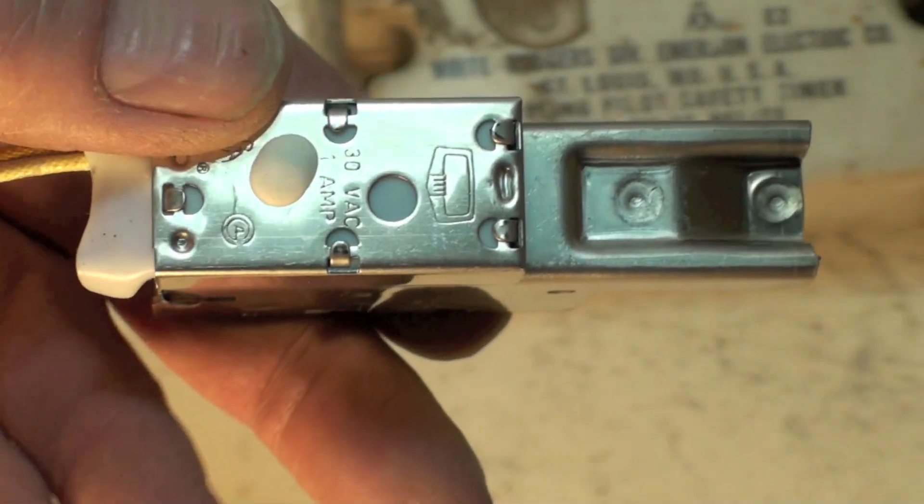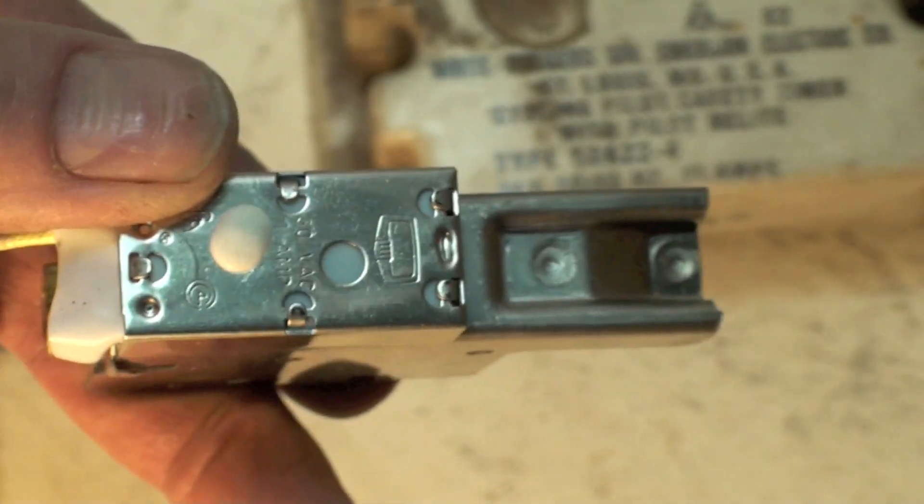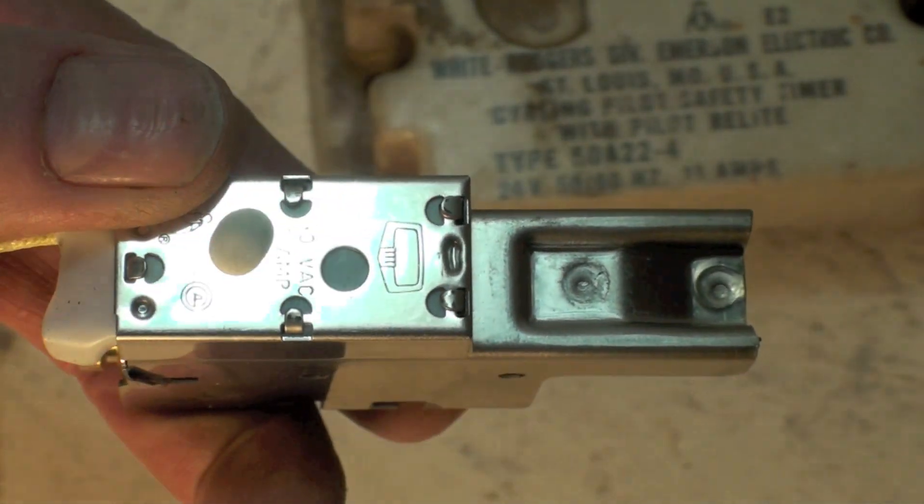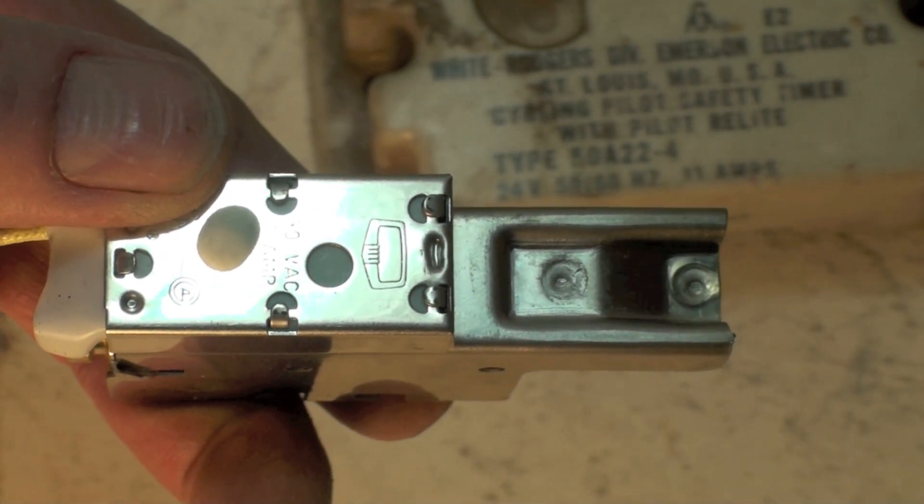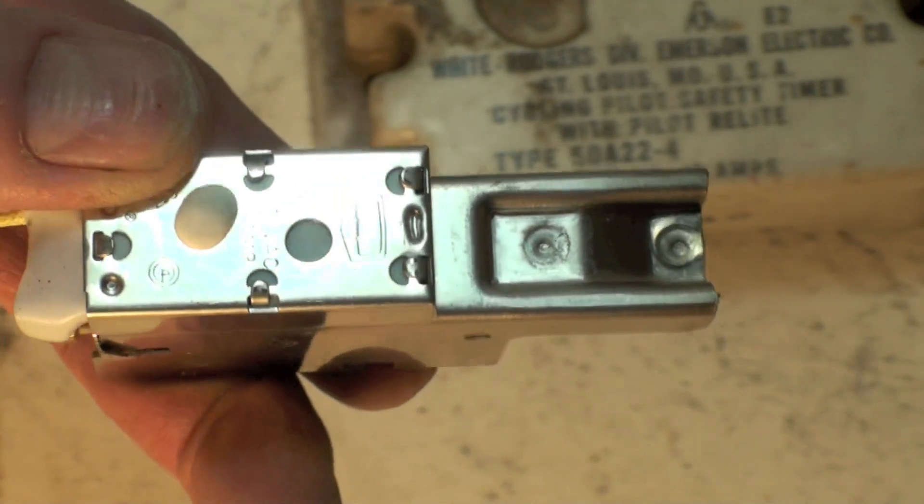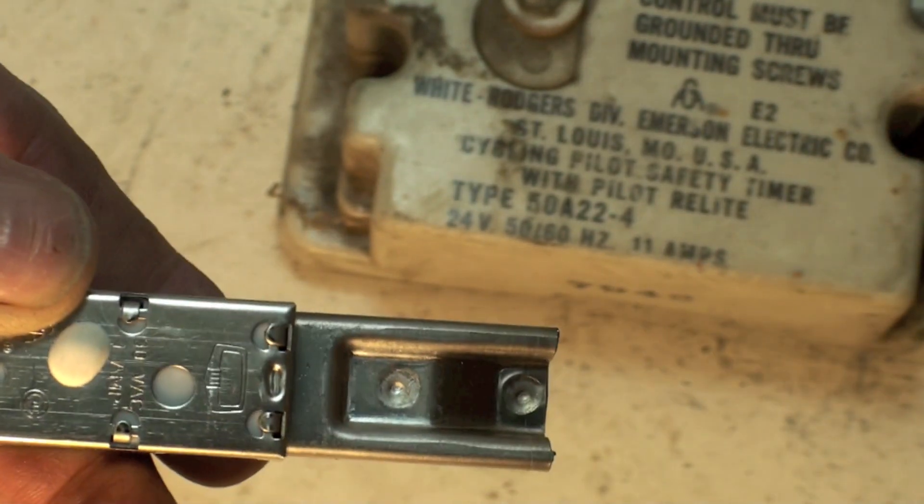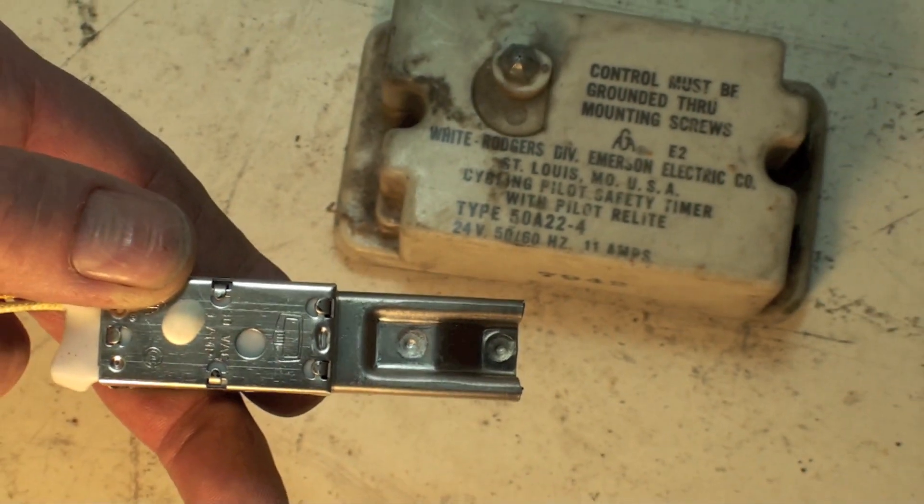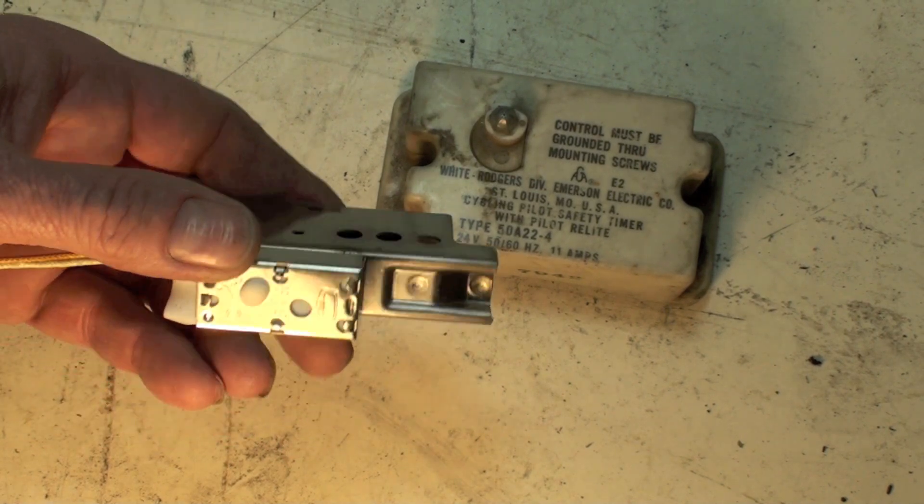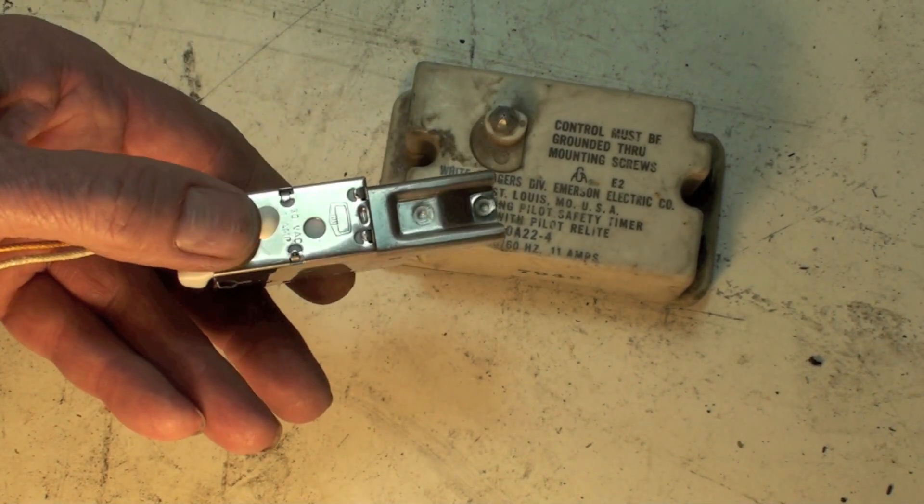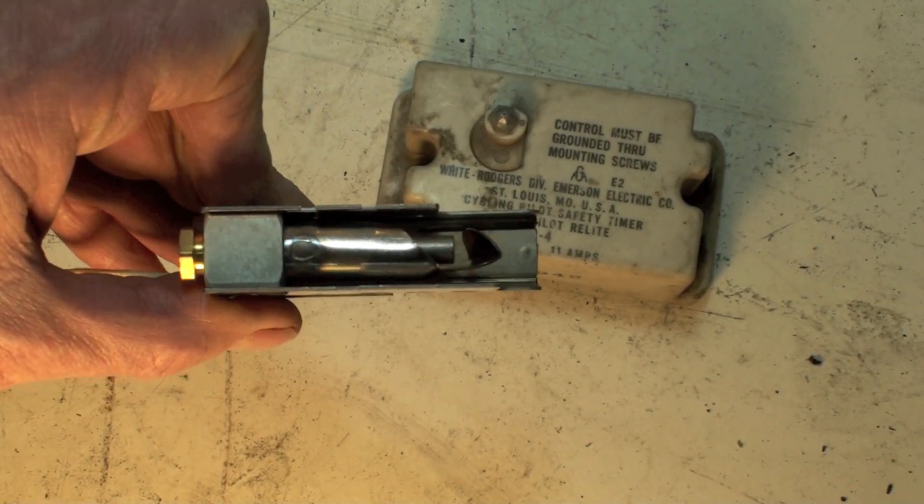So this is just a pilot relight system. A lot of them are used in commercial rooftop units that tend to get their pilots blown out and this would relight the pilot. If for some reason the spark could not relight it, then it would shut off main gas because it would lose the power from this normally open switch. When that bimetal cooled down it would shut off and the main gas would go off.